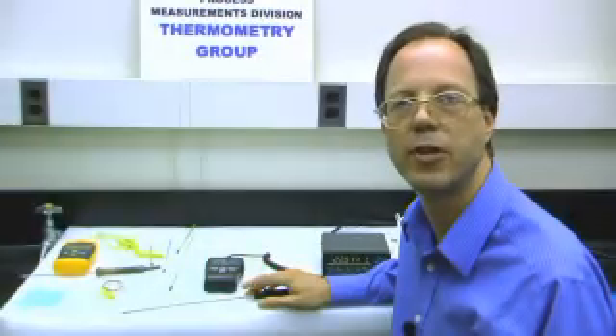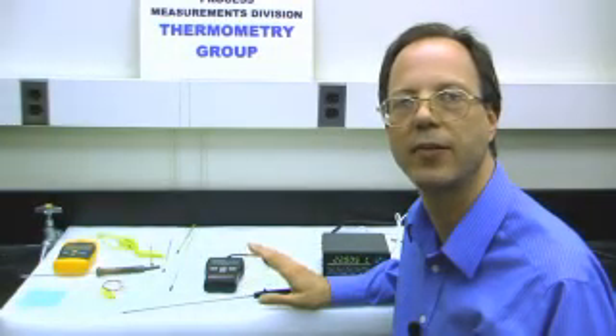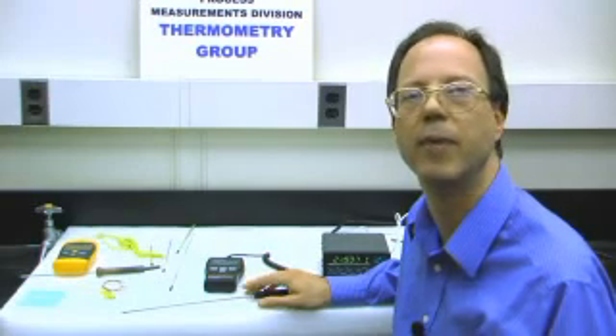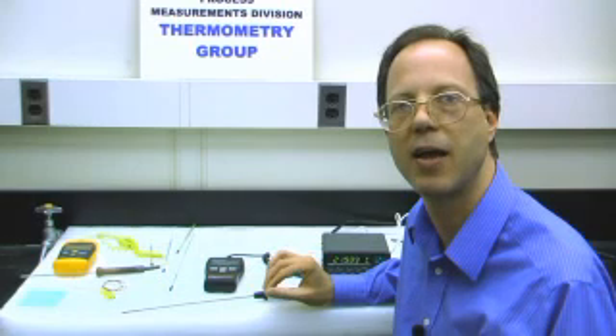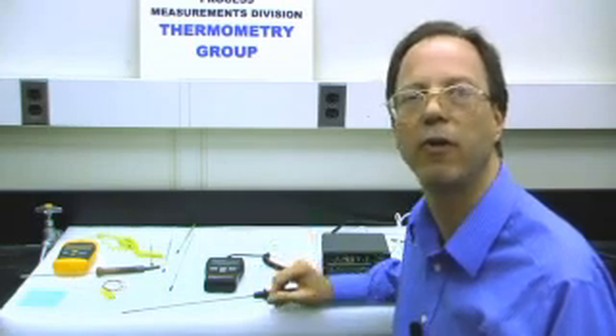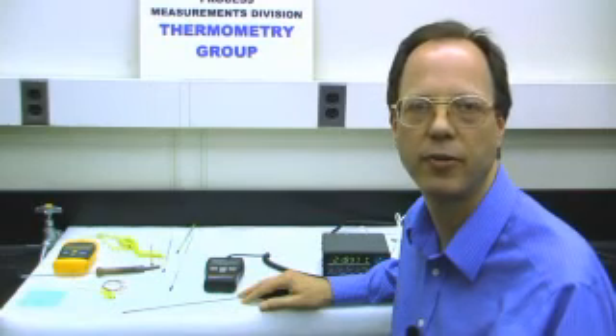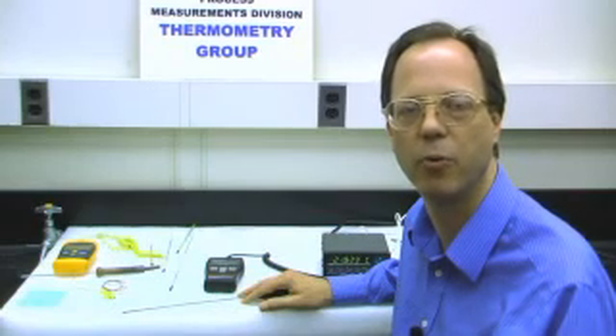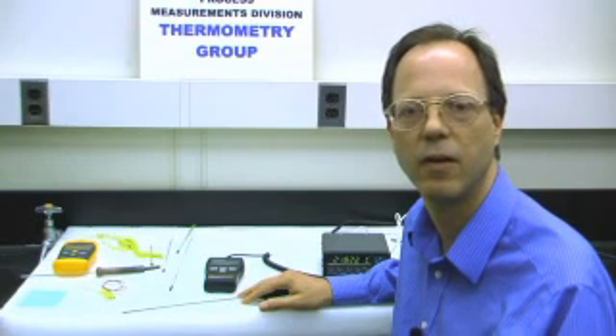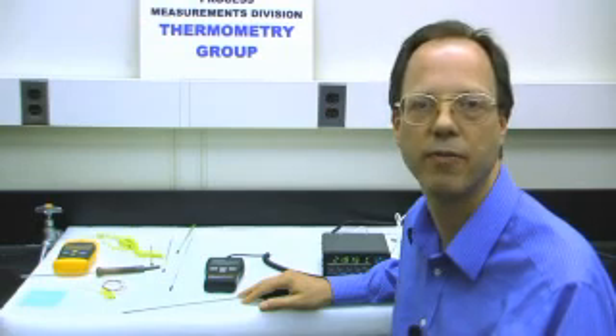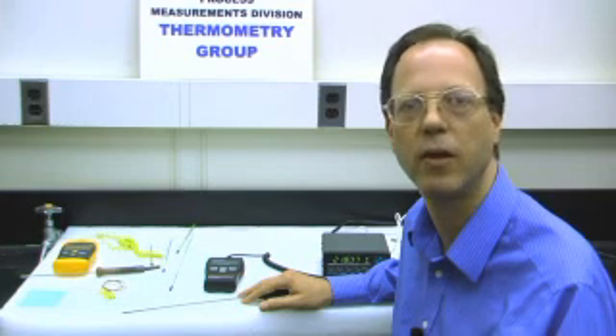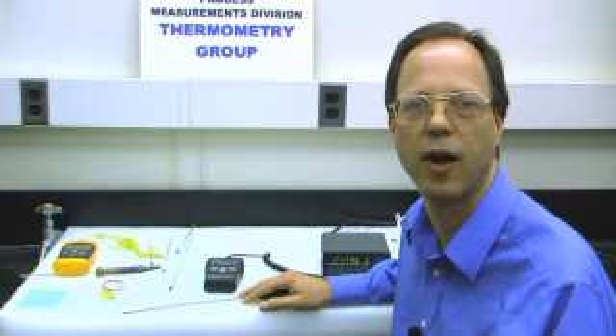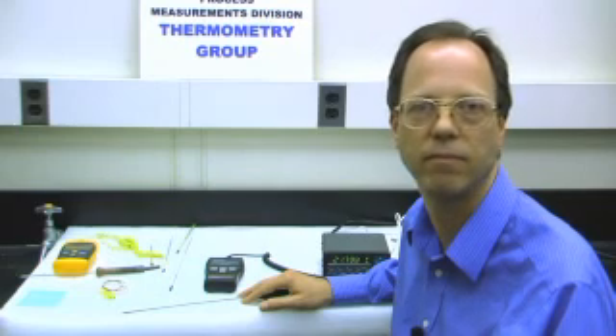In many of the thermometer types, it's also important to select the right type. For example, thermocouples come in many different types. If your readout is not selected to have the same type as the probe you're using, you'll also get the wrong answer. You want to be careful not to exceed the recommended temperature limits of the probe that you're using. You also want to check the performance of thermometers on a regular basis and have them calibrated regularly, or you can look at some of the methods we describe on the website accompanying this video.